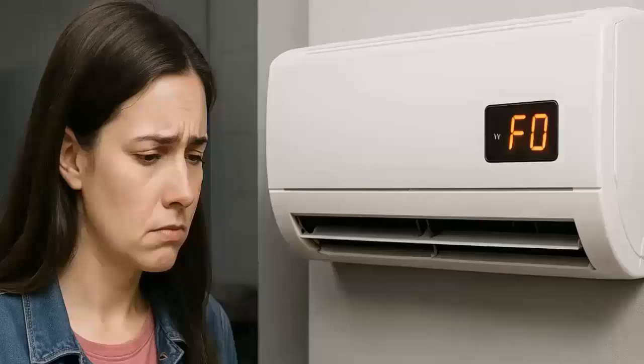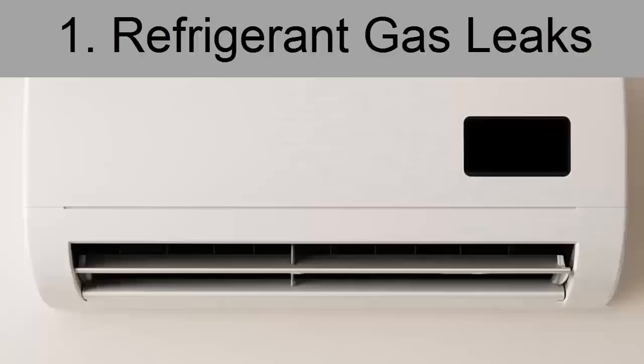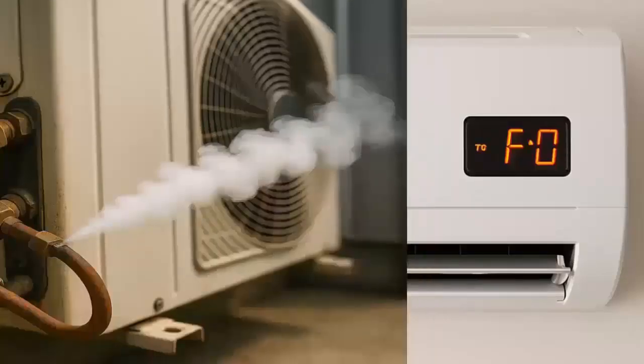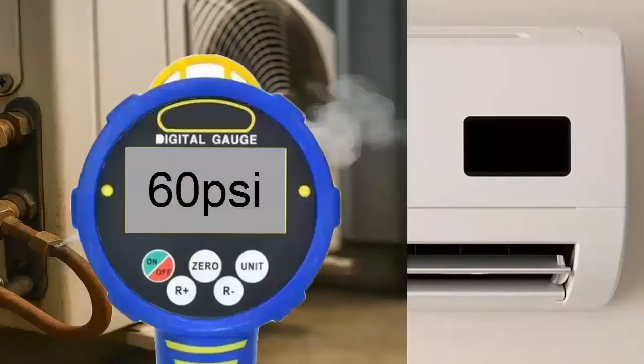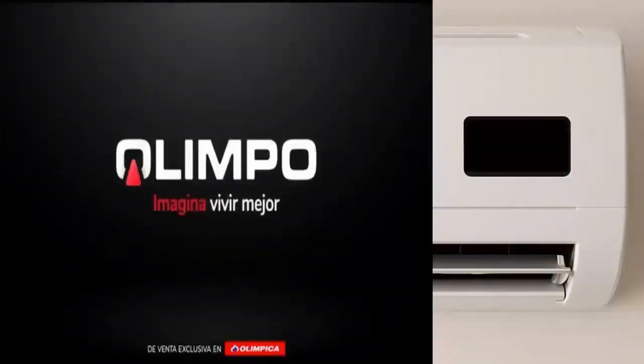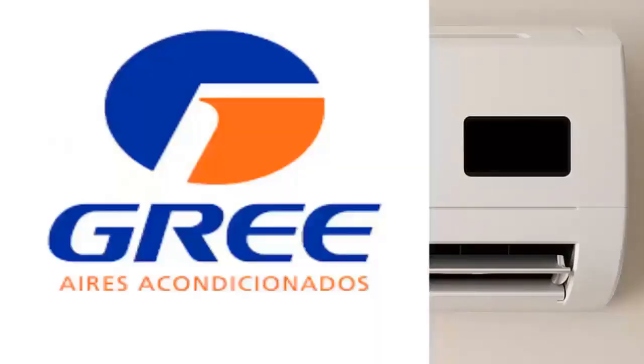First category: refrigerant leaks. There may be poor cooling due to a gas leak. If the unit uses temperature sensors to detect lack of cooling, a sensor defect can trigger a false alarm. That's why these two issues are closely related and often confused.